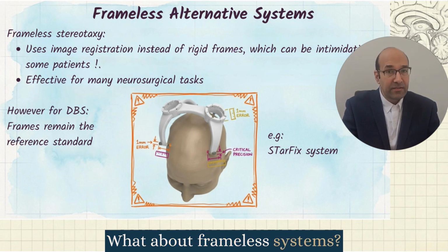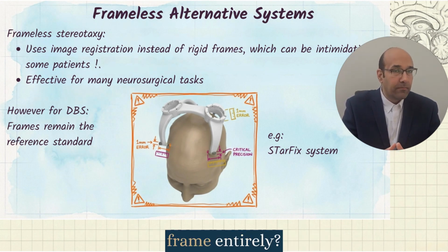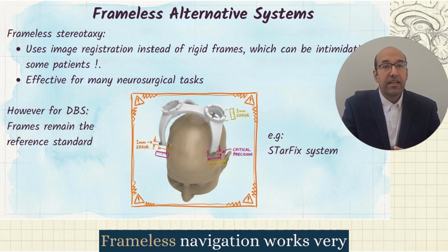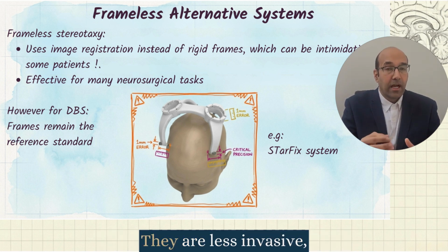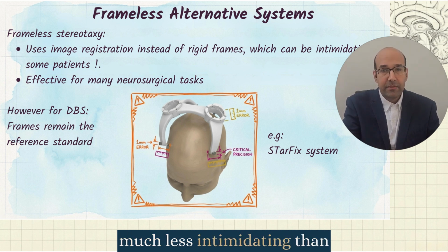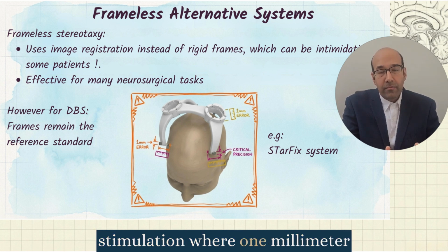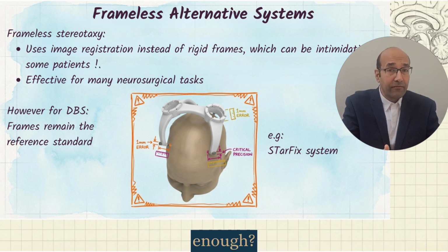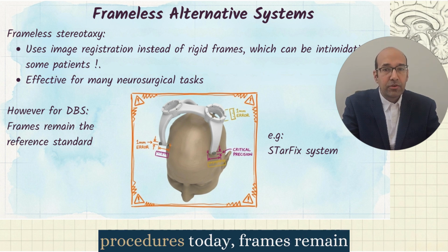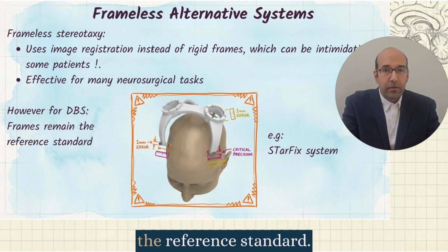What about frameless systems? Can we skip the frame entirely? In many neurosurgical procedures, yes. Frameless navigation works very well. They are less invasive, faster to set up, and for some patients, much less intimidating than having a metal frame bolted to their head. But here's the key question. For deep brain stimulation, where 1 millimeter matters, are they accurate enough? The honest answer is that for most DBS procedures today, frames remain the reference standard.